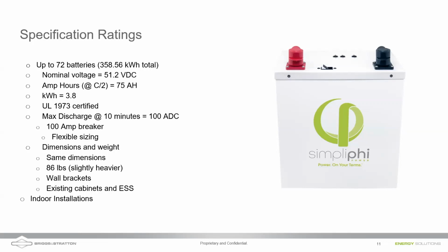So this is a 3.8 kilowatt hour unit. That means it's got 75 amp hours of capacity at 51.2 volts. So therefore you can charge and discharge at C/2, which is 37.5 amps per battery. And this is going to scale up as you add batteries to the system. So again, this is really a similar unit. It's a good choice for those indoor installations, especially in extremely cold environments where you have to have the battery indoor and insulated. You know, there's no sense in paying extra for an outdoor rated battery when you're going to be putting it in an indoor rated place.